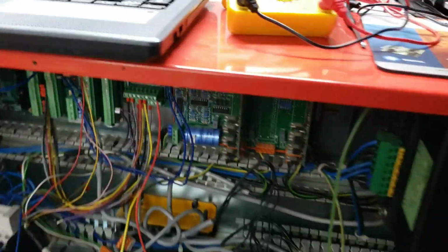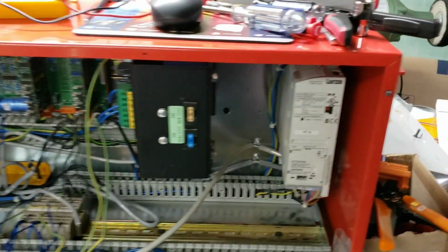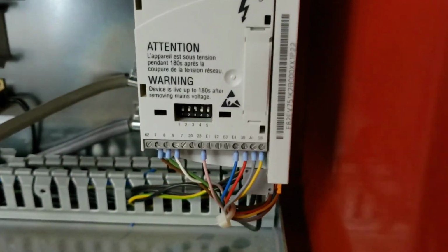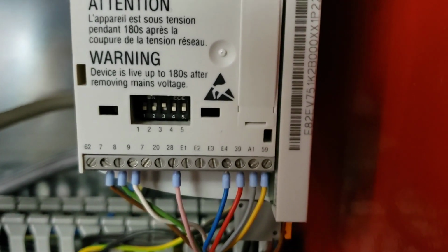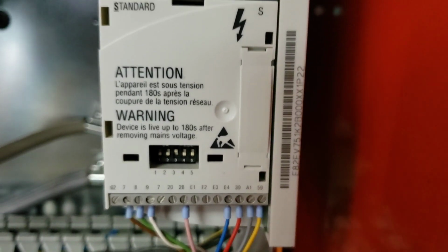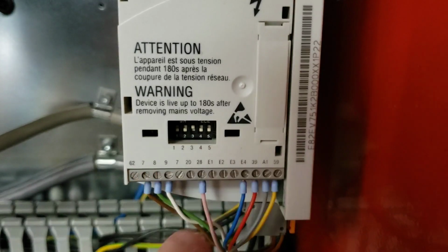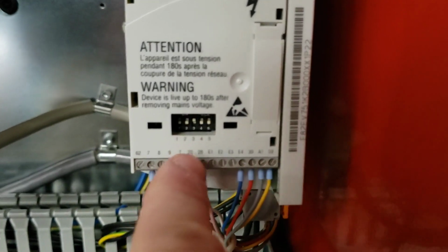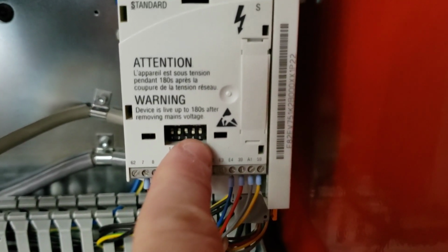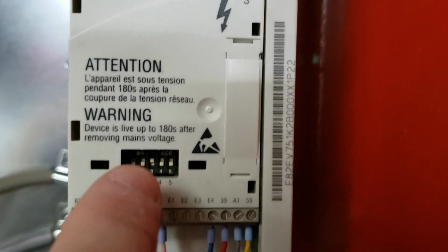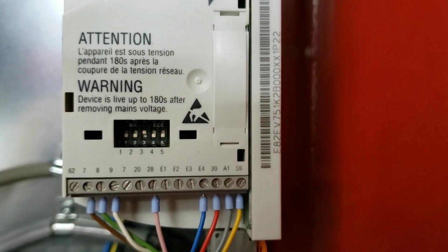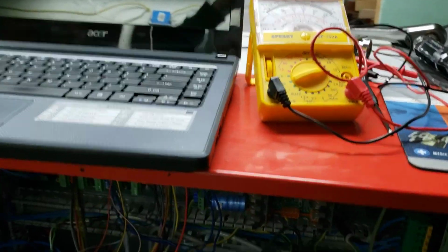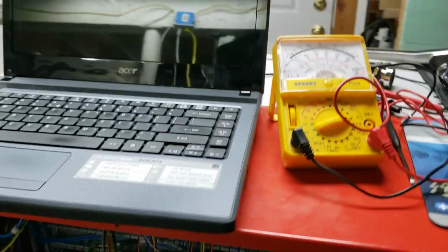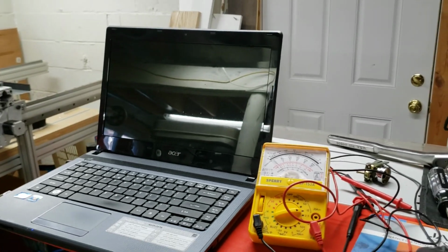It was a little different than I thought it would be, but it does work. I had to move the dip switch on the VFD unit. It was set up for 10 volt, and I've only got a 5 volt potentiometer. If I had 10 volt going into this, I would have to flip dip switch number 5 back up. That was really the only difference there. It runs strong. I'll fire it up and take a video of it running.